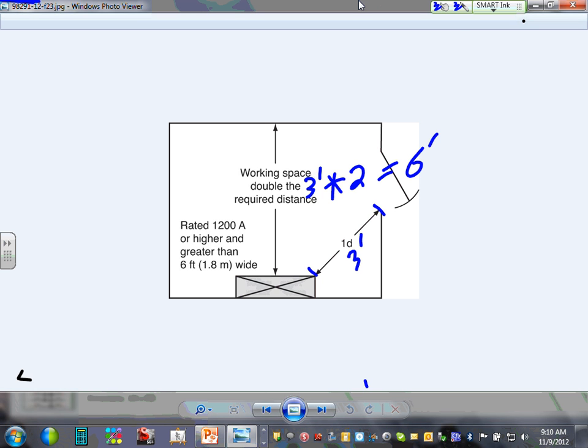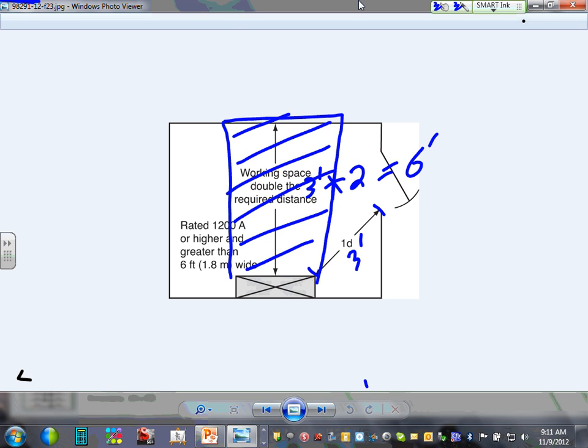Why do they care about, guys, 2 entrances for bigger equipment? They don't want you to be trapped if there is a big ball of fire coming out of the equipment. What I'm talking about, guys, here is a big deal when we design systems. So what the engineers do is they go right in the front of the equipment, guys, and they draw a box and they hash it. And they put 6 feet on it. This means do not install anything in the front of the equipment.